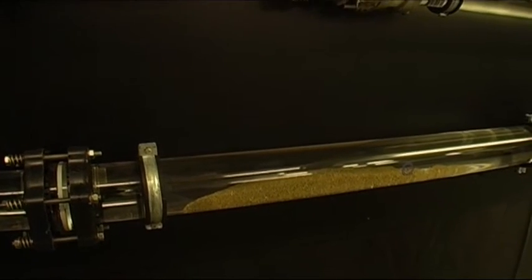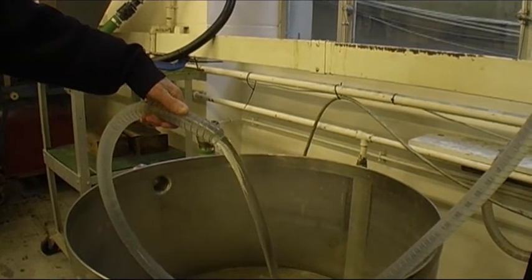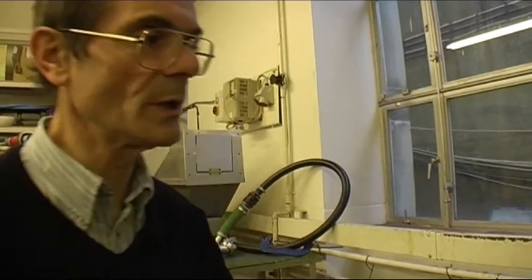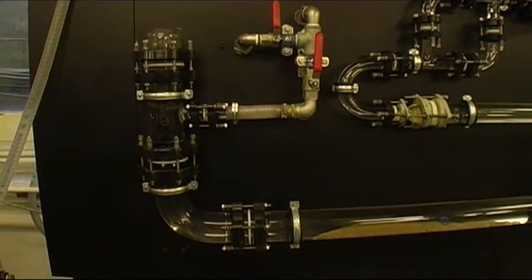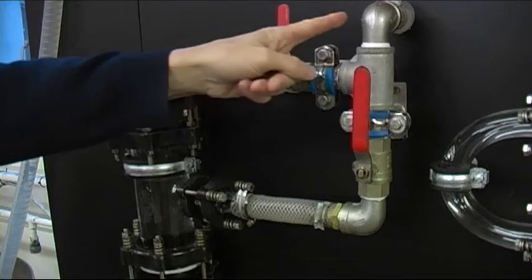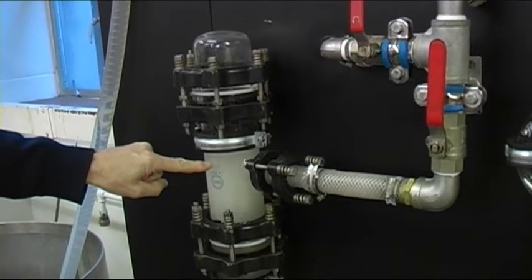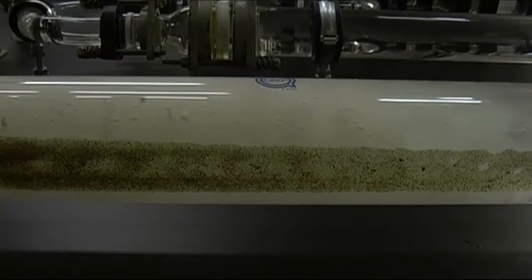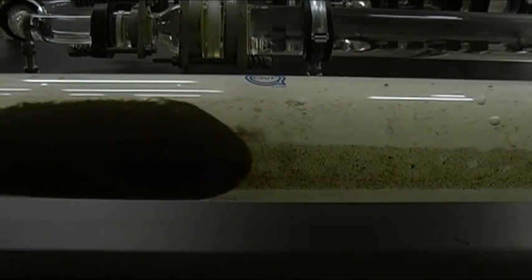The amount of water actually going through after it's been through the system gives you an idea of what the flow rates are — not very much, but not unrepresentative. What will happen now is that we'll switch from water to the ice pig, the ice slurry, at roughly the same speed and the same volume flow rate. Ice will come down here and start filling — you can actually see the slurry now. This is very weak slurry but it's getting thicker and stronger. That slurry is unable to move the sand so it's still a slushy pig, getting thicker and thicker — and there it goes.